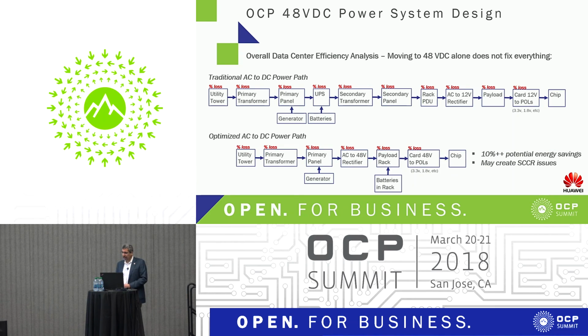So looking at the same arrangement, just copy, the line on top is the exact same one as from the previous slide. And just for comparison, you're saying, well, what if we try to optimize the entire AC to DC power path? What if we did only one primary transformer, right? But instead of being 480, it's maybe a 415 transformer. 415, 4-wire transformer, you get 240 right on the output. You don't need a secondary transformer, so got rid of that.